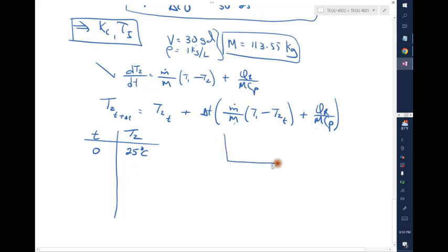As I was saying, you start here. Let's say that the CO was changed. This is time. You change the CO to 50% here, and then this will start to rise to get to the first steady state. Now, whatever you do after you get to the first steady state, you can go up or down. If I go up this time, and I go to 75% on the CO, this is CO and this is PV. What's going to happen is, starting from where I did the change, let's say the change was here, this will go up to a second steady state. So I have a first steady state here and a second steady state here. All right, so this keeps going this way.